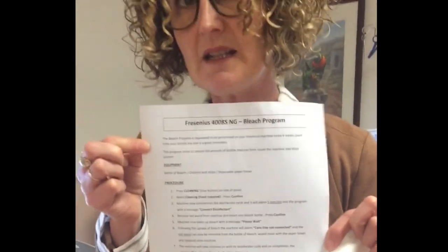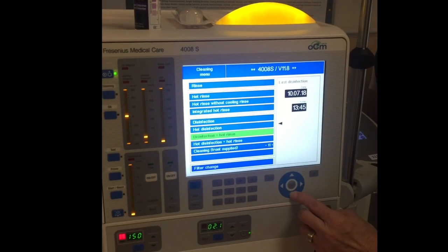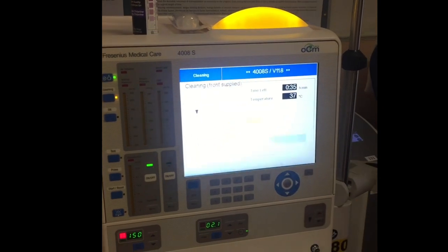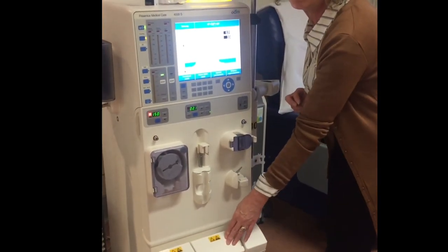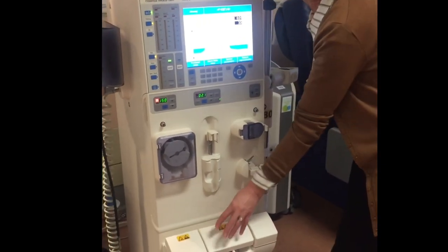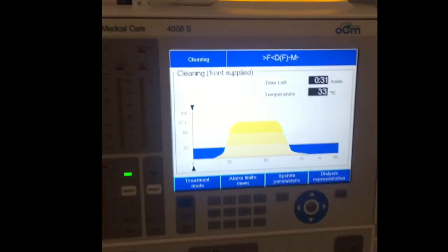I've already turned on the machine. This protocol is all in your machine maintenance section of your manual. We're going to press 'Cleaning' and find 'Cleaning Front Supplied' on the front screen, then confirm. What 'Cleaning Front Supplied' means is that it's going to pick up the bleach from the front of the machine — not like the citric acid at the back. This time we get our bleach from the front.